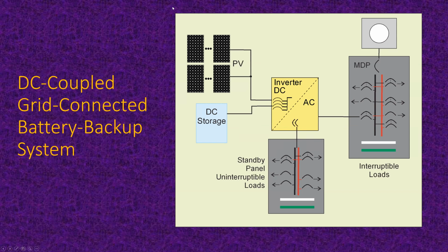Well, anyway, hopefully this explains how much more simple this whole thing is. I mean, this DC storage is all in one box. All the charge controllers, everything, the battery management system, it's all in that box. You get DC out at about 400 volts to the inverter. PV comes in at about 400 volts. Notice it's all on the same bus bar here. We can connect more PV or more storage. We've got 4 circuit breakers here for connecting stuff.